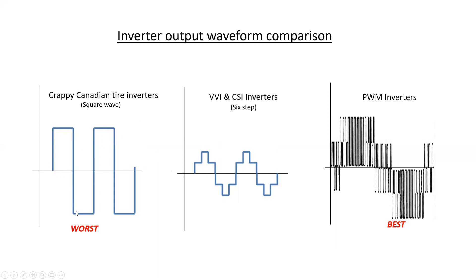VVI and CSI inverters are referred to as six-step because the voltage applied out of the inverter is in six steps — one through six — going down on the negative and up on the positive alternations. PWM is actually the best AC sine wave generated by an inverter, though it looks a little bizarre, and we'll take a few moments to investigate further what exactly is happening with it.